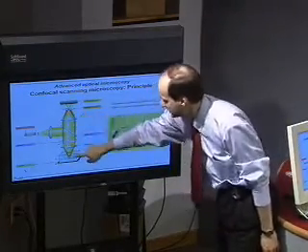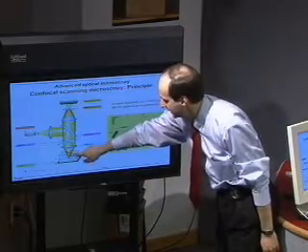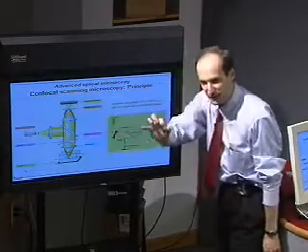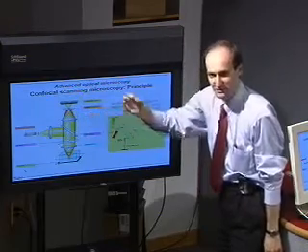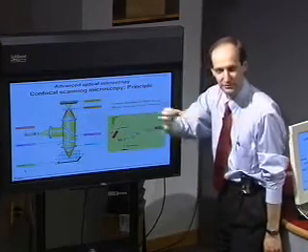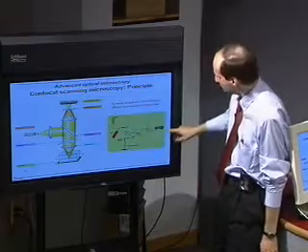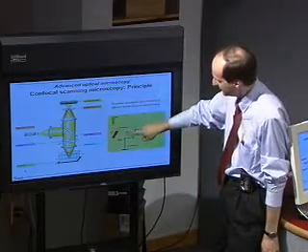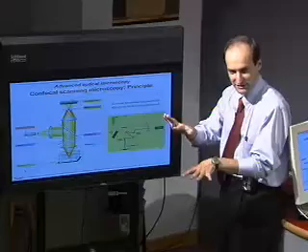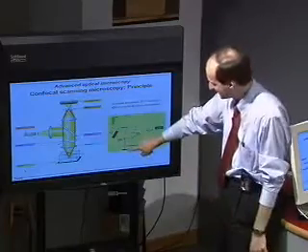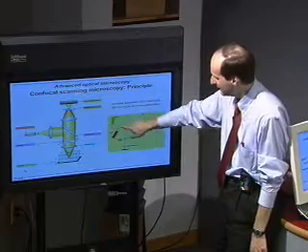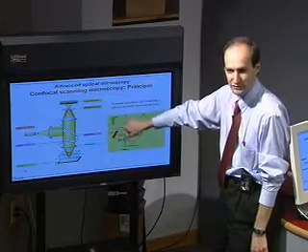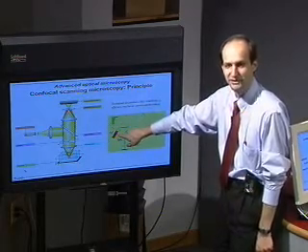You have a light source, illumination, laser. You have a very strongly focused beam. It scans the sample. In this case, you have this pinhole here. So you can scan by moving the pinhole. In reality, what happens is the laser light goes through these 2 mirrors, which scan the sample around. Then it gets reflected back, and then it hits photomultipliers. You may have different photomultipliers for different wavelengths.